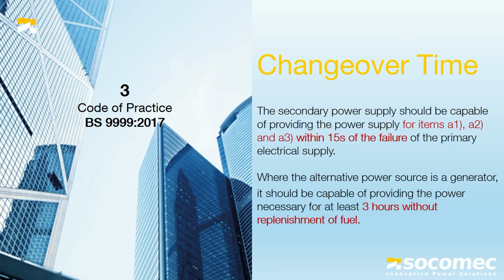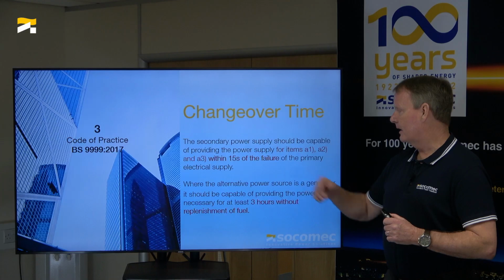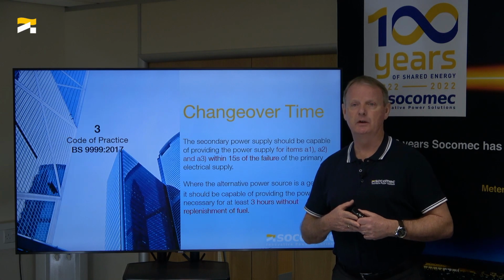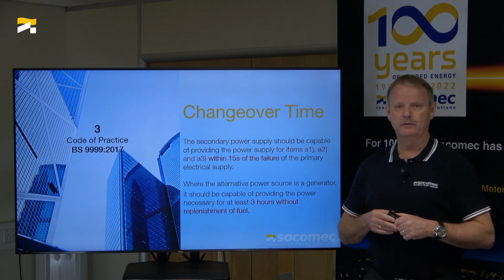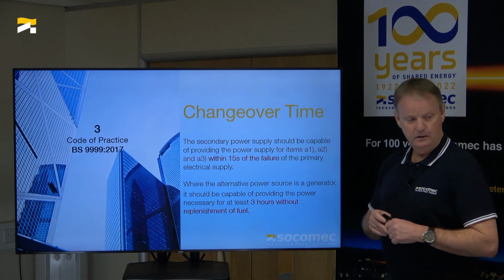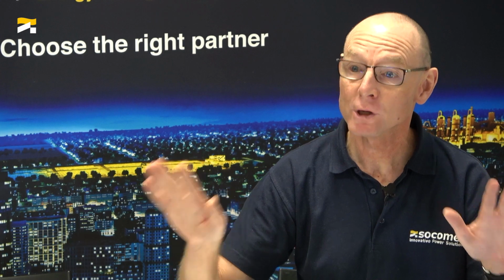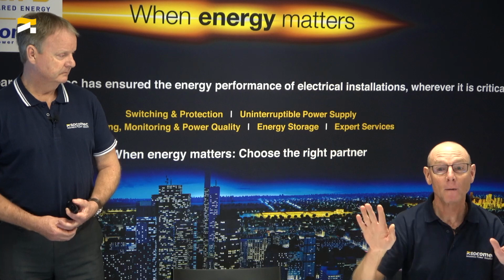What it says here is the key part, which is why it's in red: it must be within 15 seconds of the failure of the primary supply, so it doesn't need to go straight away. Quite often the second source - if you remember the picture from one of the slides further back - would be a generator, which takes up to 15 seconds to get up to speed and ready to be the second source. But it doesn't have to be a generator - you could have 2 supplies, as long as they're from separate substations with a 2-hour fire rating between them. So 15 seconds for a generator, but you could have 2 substations.